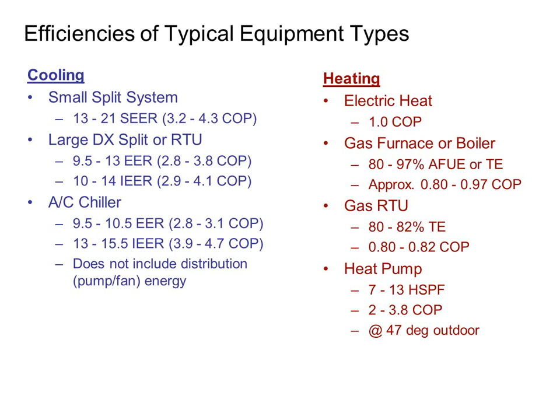For the small residential size ones, 5 tons and under, they're rated in HSPF. For sake of argument today, that's basically the SEER of the heating world. How efficient is your unit as we cycle it through the various modes of heating? The bigger stuff that's more than 5 tons of capacity gets rated in COP, coefficient of performance. And it's very common to see ranges of those. In this case, 2 to 3.8 is the range I put up on here. The temperature at which you choose to test it affects the coefficient of performance, just like it would on a cooling system. If we tested it at something hotter than 95 degrees out, it would lower the EER and COP numbers. For heat pumps, they test them at 47 degrees, and then usually they also test them at 17 degrees to give you an idea of how the energy and capacity are scaling.